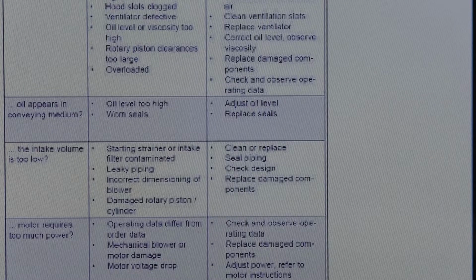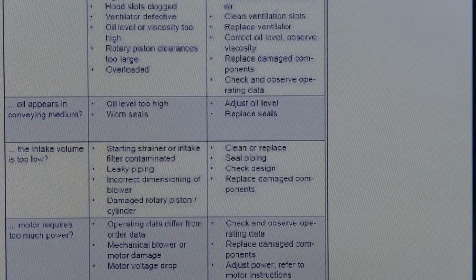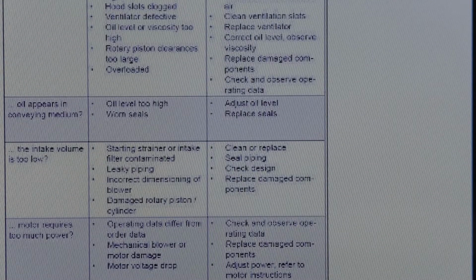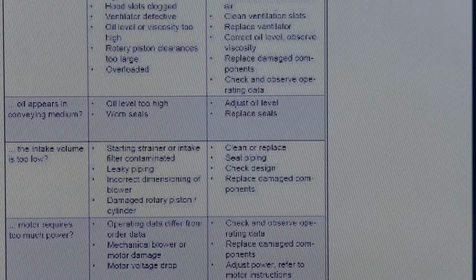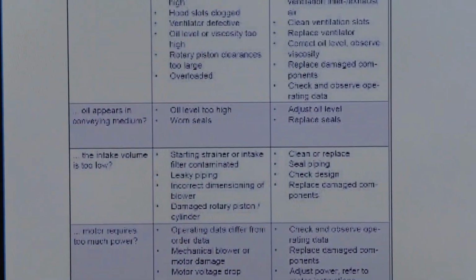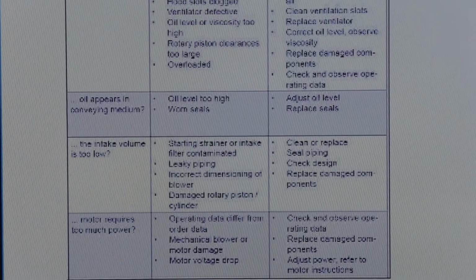If there's an electrical issue, say you get a VFD failure, and on the display it tells you that there was a voltage loss or something along those lines, you're going to also have that same potential alarm on the blower. Now, that's not a guarantee, because the control power and the main power are separate items, and the drive does not directly communicate with the Aerzen control. So the VFD fault will not show up on the blower control panel. It only shows up on the front of the VFD and on SCADA. All right, go ahead and go to the next one.